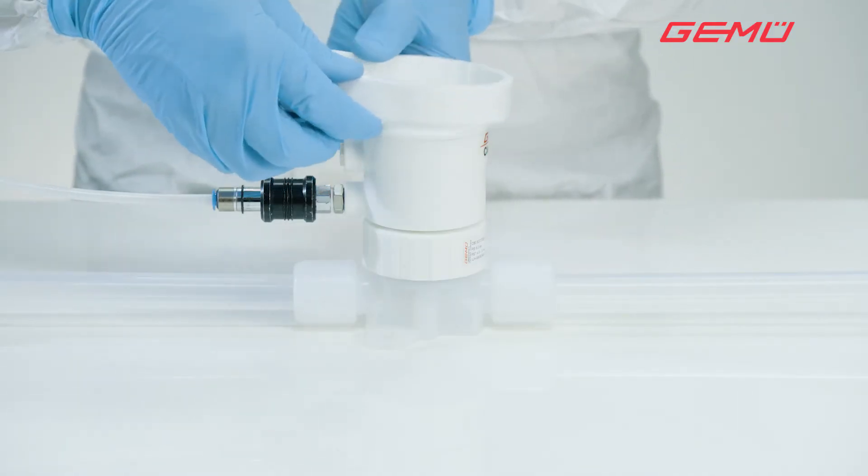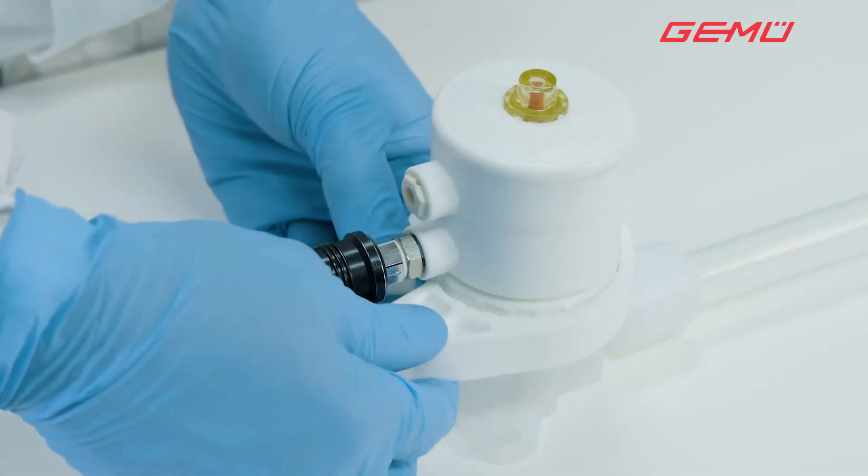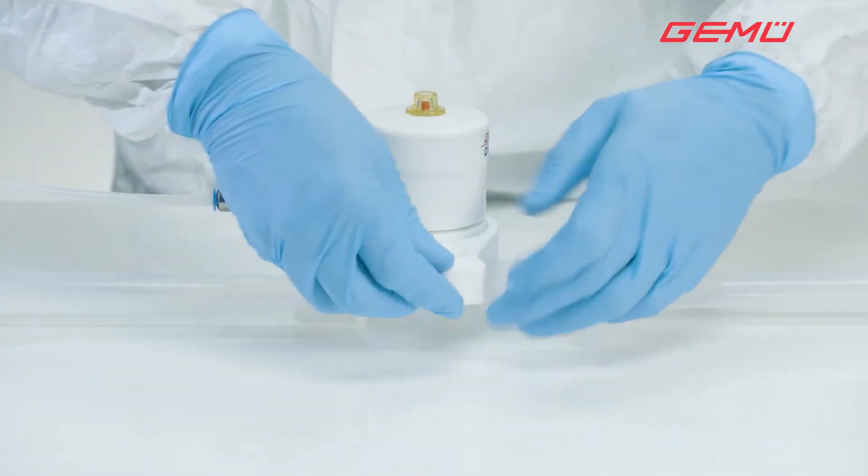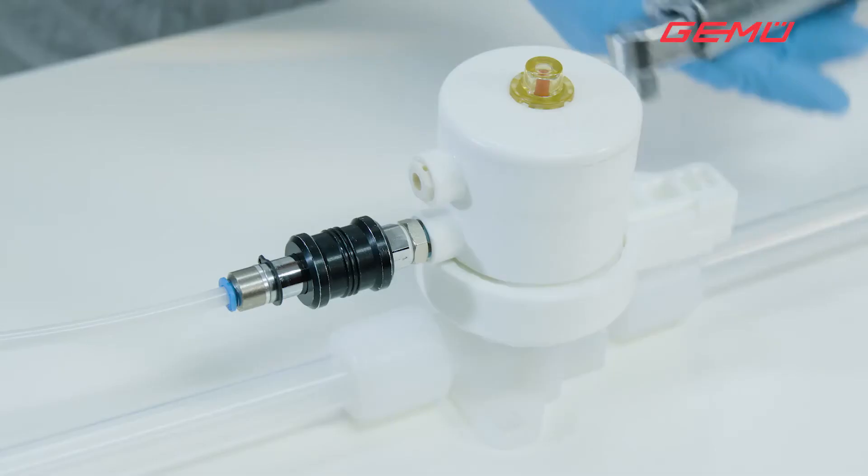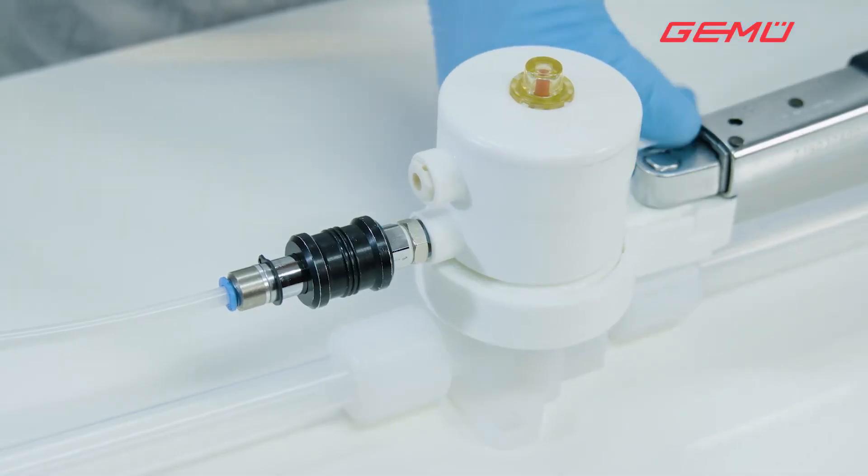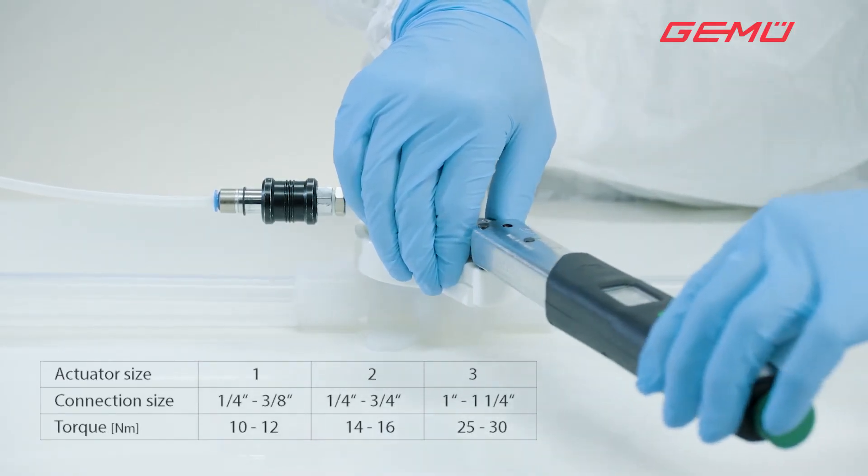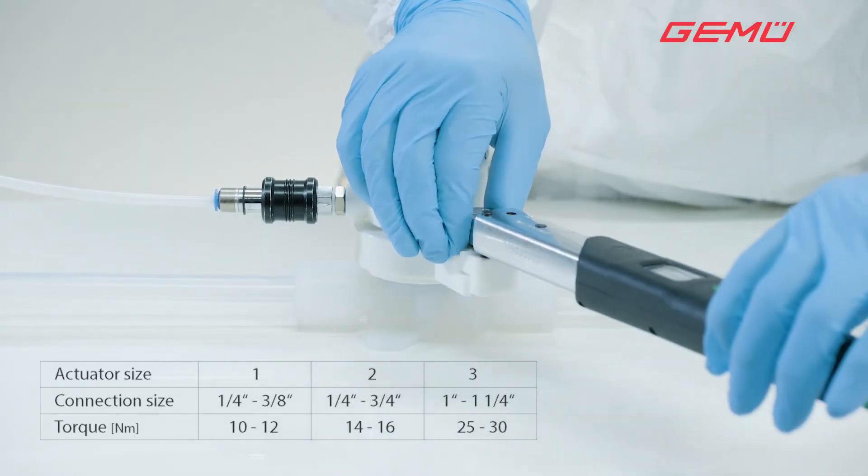Position the GEMÜ service tool in the correct position on the central nut and attach the torque wrench in the extension for the service tool handle. Failure to do so will result in an incorrect torque. Tighten the central nut to the specified torque.